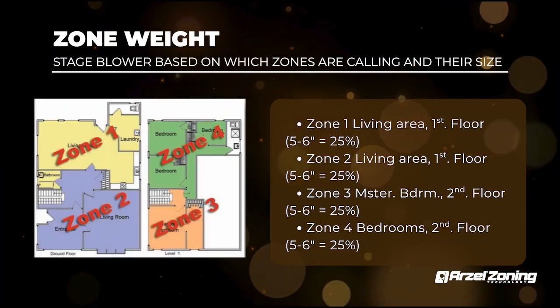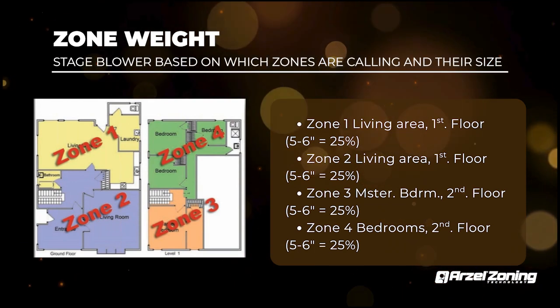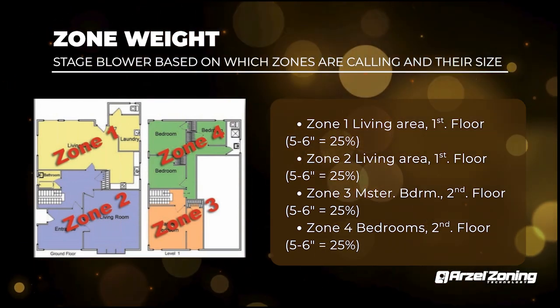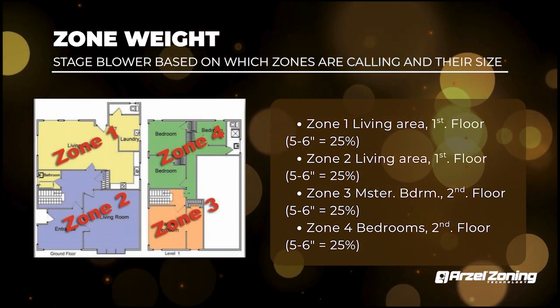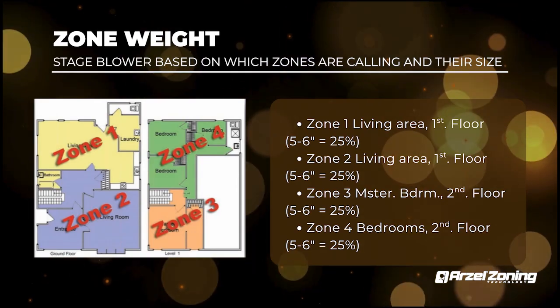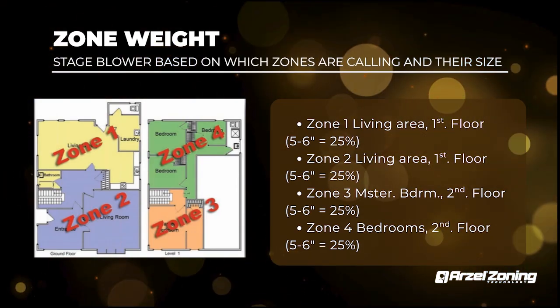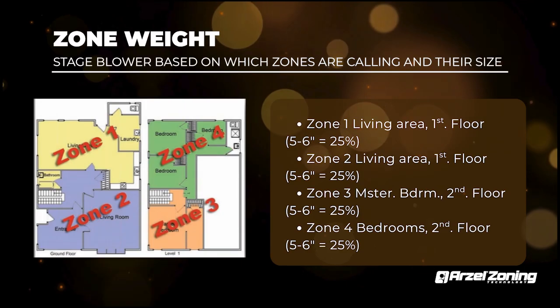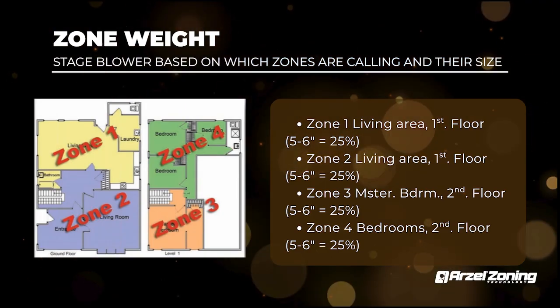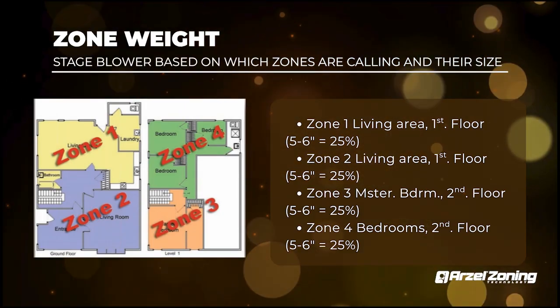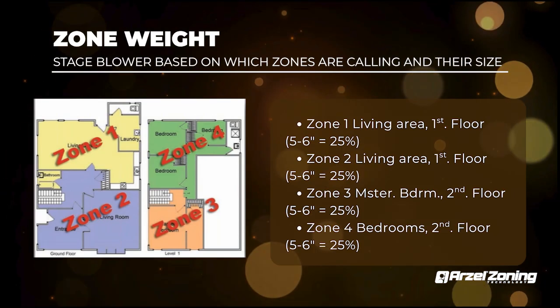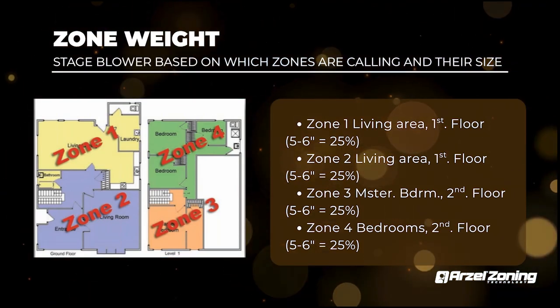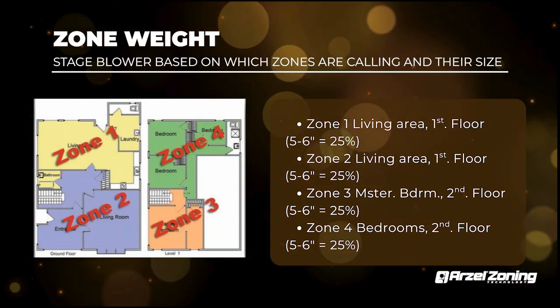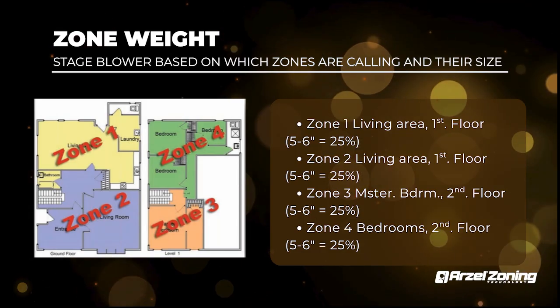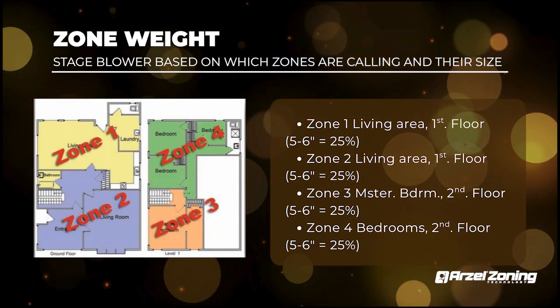So really, it's a really easy feature. Essentially, what it's going to do for you guys is you're going to have a zone weight percent for each of your zones. To sum it up, the easiest way I can tell you guys is that's going to be a percentage of ductwork per zone. So if you have a 4 zone, just figure out how much ductwork is on each zone and create a percentage for that. In this case, each one is at 25%, so they're pretty even zones. So we got zone 1, zone 2, zone 3, and zone 4 all set to 25%.